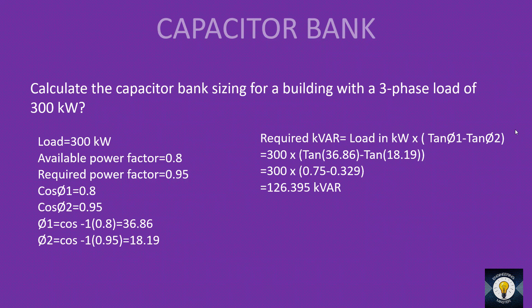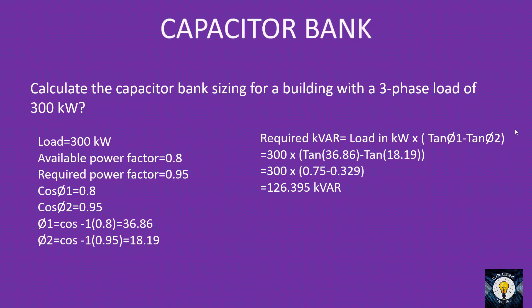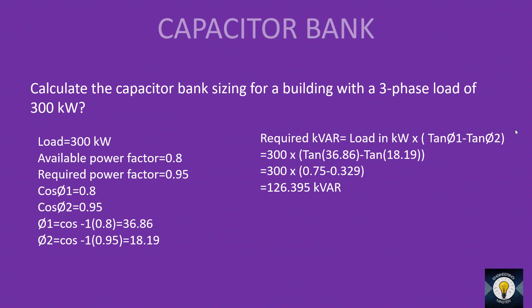So our required capacitor bank, lifting power factor from 0.8 to 0.95 with a load of 300 kilowatt, is 126.395 kVAR. As an MEP or electrical designer, this sizing is sufficient — just provide it to the capacitor bank manufacturer. But if you want to learn more: the SI unit of capacitance is farad, so we need capacitance in farads.